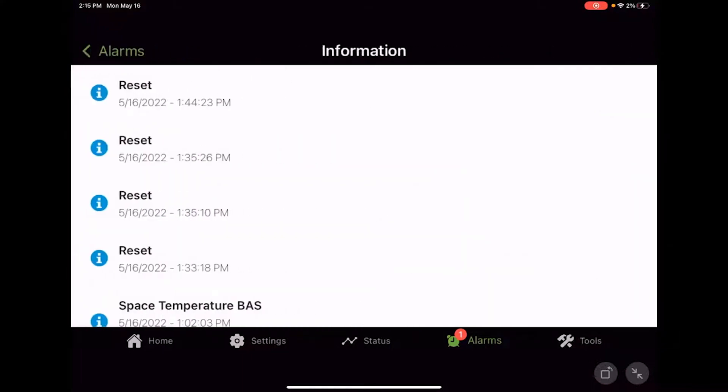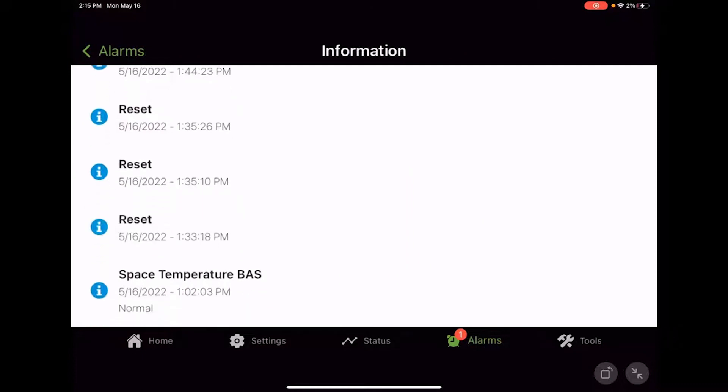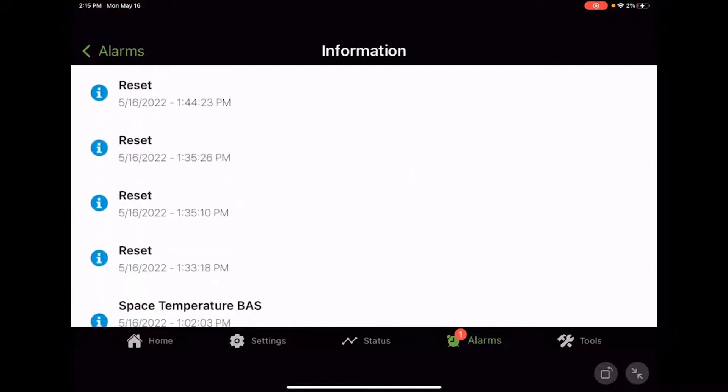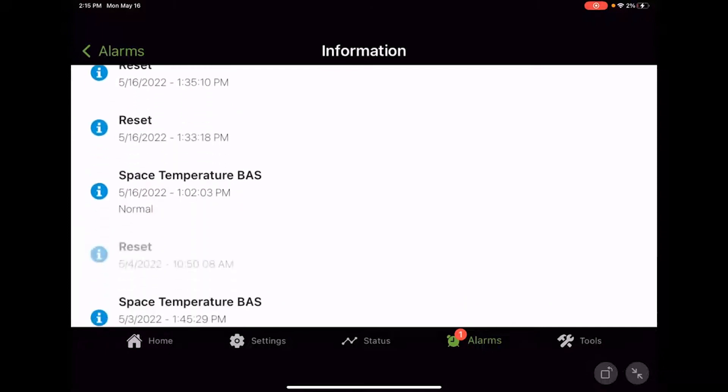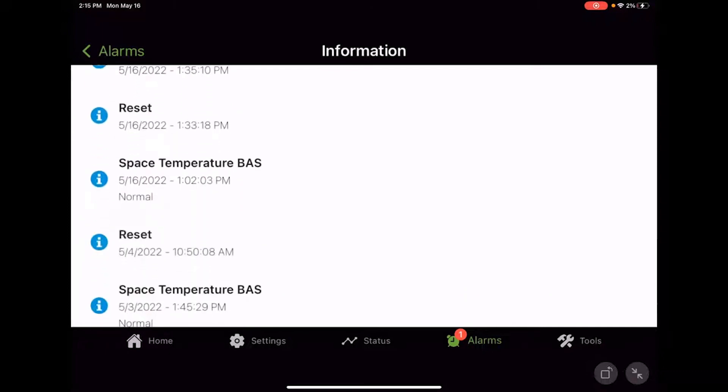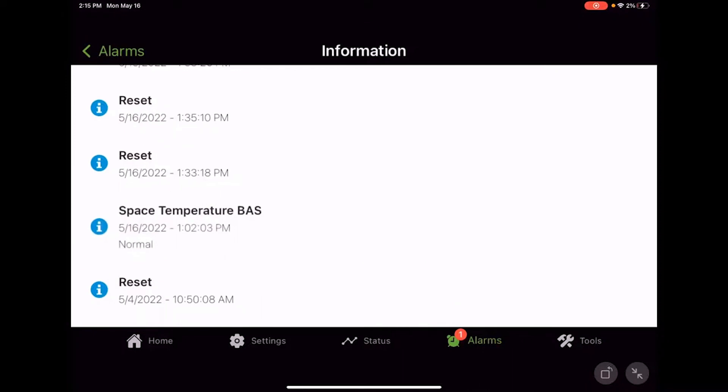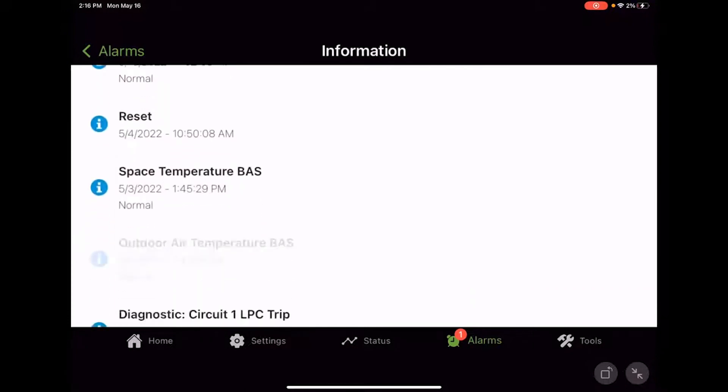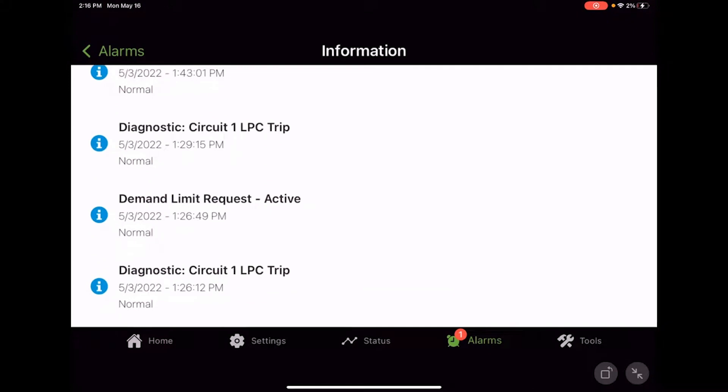And then we've got informational and that literally is just information. So obviously today I've been playing around making some videos. So we've had some controller resets throughout the process here. We had some stuff with the space temperature BAS I was playing with earlier in another video. I think maybe if you checked that one out when we were going through settings, I changed the unit from BAS to local control and vice versa. So that's probably where we got some informational. These are really diagnostics, but they're really just information. This thing happened. We got a demand limit request. It's active. It's not really a diagnostic. It's just saying, Hey, this happened at this time and on this date.